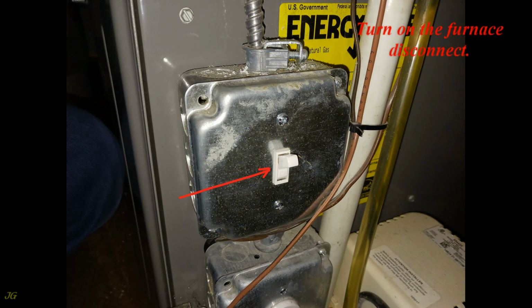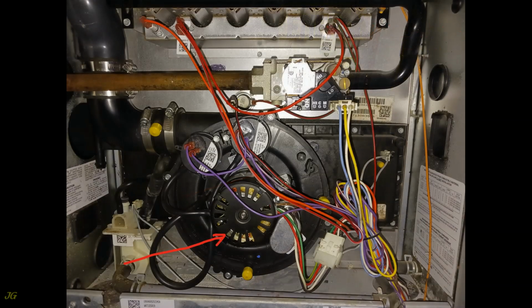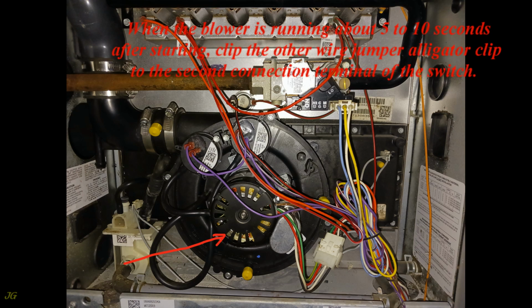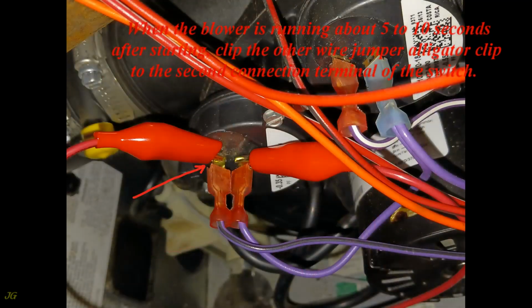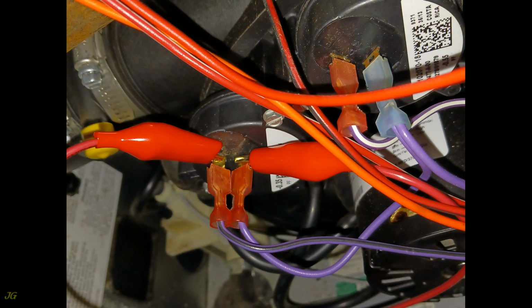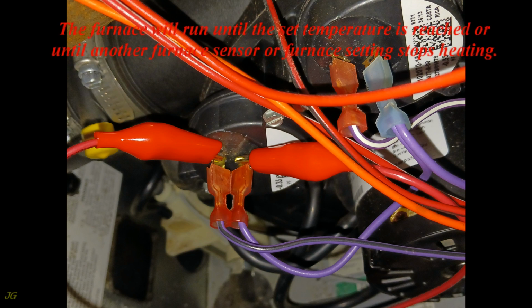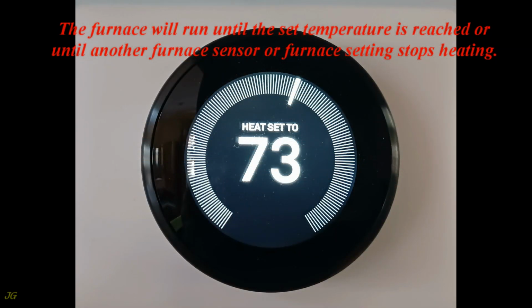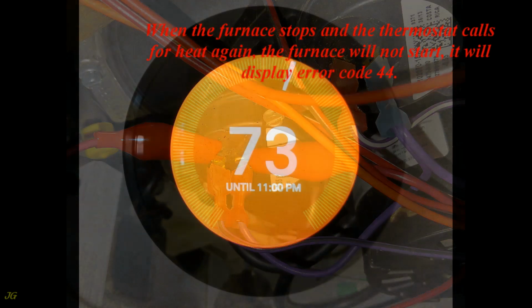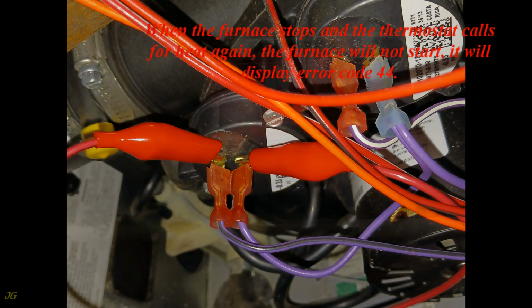Turn on the furnace disconnect. Wait until the draft blower turns on. When the blower is running about 5 to 10 seconds after starting, clip the other wire jumper alligator clip to the second connection terminal of the switch. The furnace will run until the set temperature is reached, or until another furnace sensor or furnace setting stops heating.